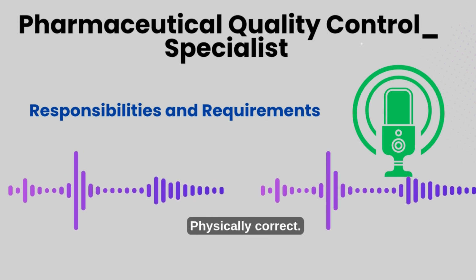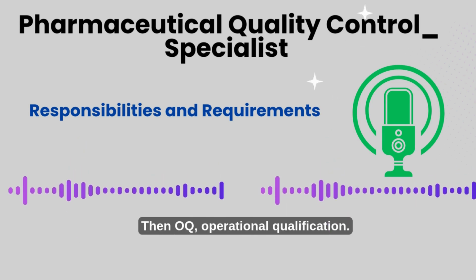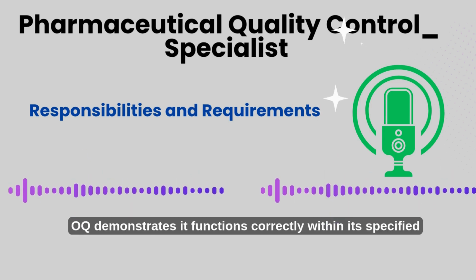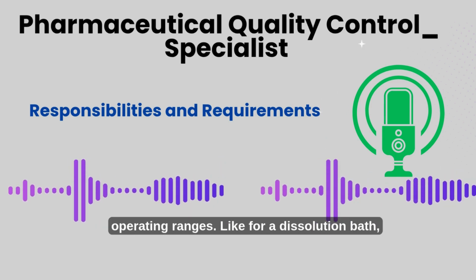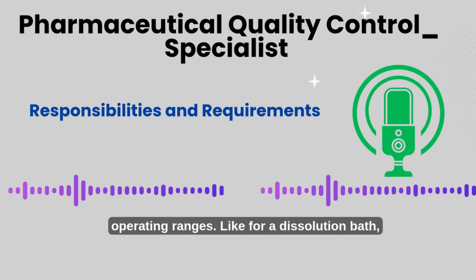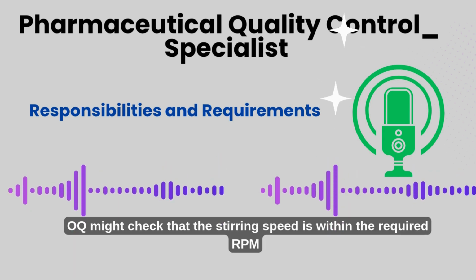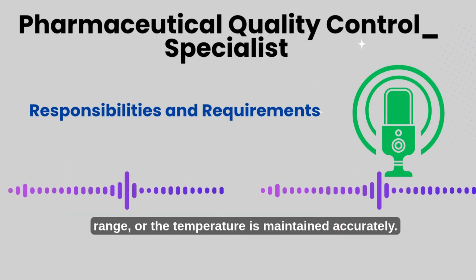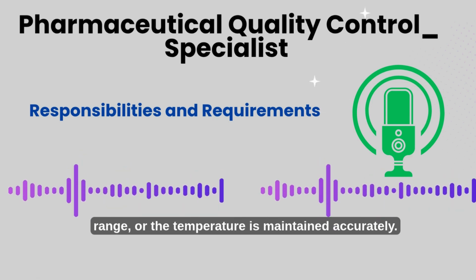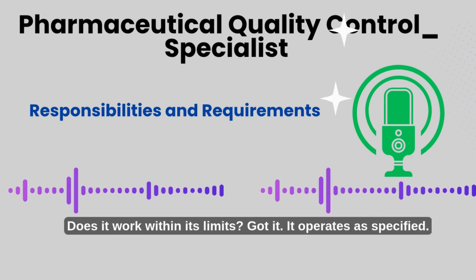Makes sense. Physically correct. Then OQ, operational qualification. OQ demonstrates it functions correctly within its specified operating ranges. Like for a dissolution bath, OQ might check that the stirring speed is within the required RPM range or the temperature is maintained accurately. Does it work within its limits? Got it. It operates as specified.